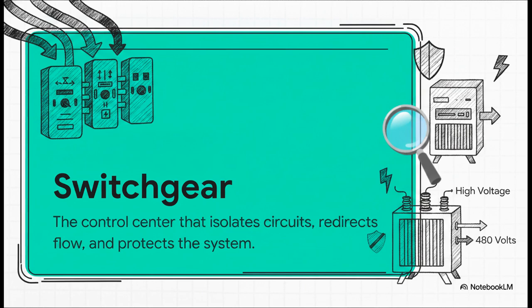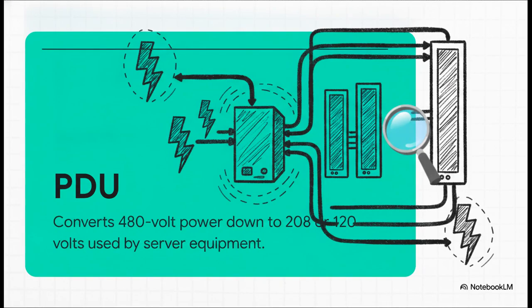Right after the switchgear, step-down transformers drop that intense high voltage down to a more manageable 480 volts. From there, that 480-volt power hits the power distribution unit, or PDU—the final major translation step. The PDU converts that 480-volt power down one last time, usually to the 208 or 120 volts actually used by the server equipment. From here, the power travels safely through branch circuits and goes right into the server racks.